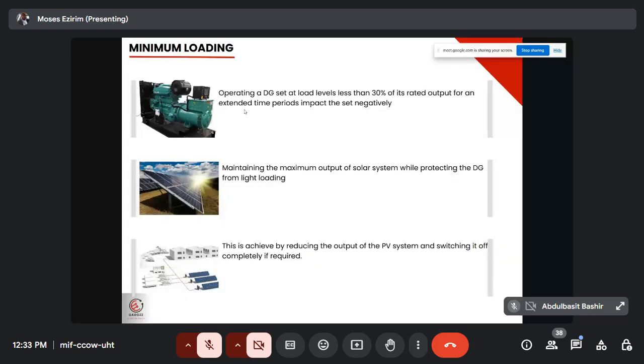If you go to almost all the manufacturers that we have around, they are using PV diesel. It's working. So you can integrate seamlessly. It will not impair that generator. Now, consider load levels less than 30% of rated output for an extended time period. I just use 30% here. Some generators can be 20%. Some generators can be 25%.